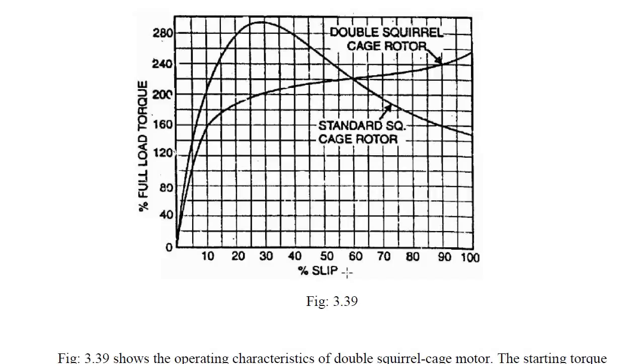This is the graphical representation of full load torque versus percentage slip. One graph is for the standard single cage squirrel cage rotor, and the other is for the double cage squirrel cage rotor. We can see that the starting torque is much higher in the double cage type compared to the standard squirrel cage rotor. This is the main advantage of the double cage construction — the disadvantage of low starting torque in the standard squirrel cage is overcome.